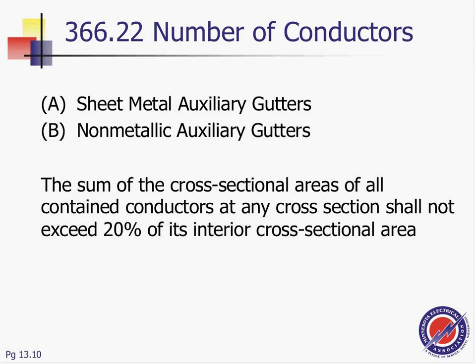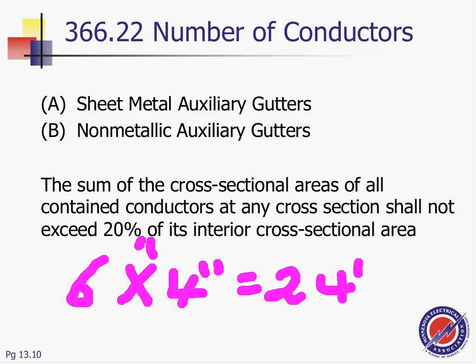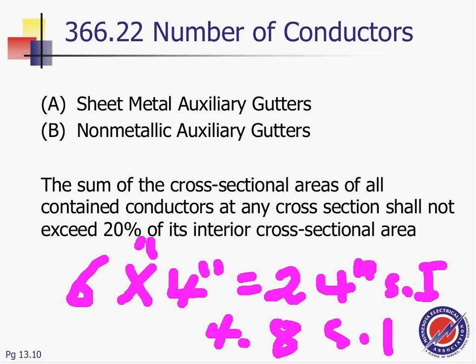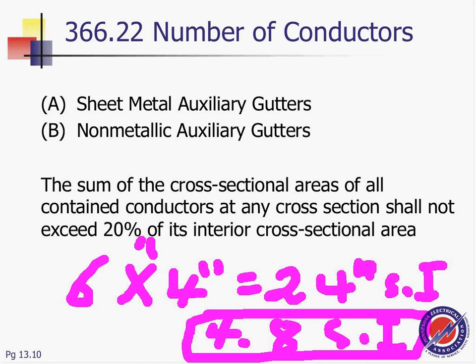So if you have, say, 6 by 4 inches, that gets you 24 square inches, and then you take 20% of this, 0.2 times 24. You can only fill 4.8 square inches. What that means is I can go and find the cross-sectional area of all these conductors, add them up, and the total shall not exceed 4.8 for this auxiliary gutter. Okay, so basically, I don't know if we have it in here. So that's basically the fill for them.